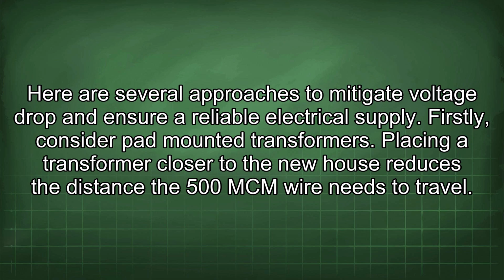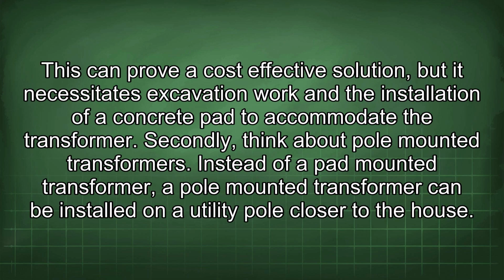Firstly, consider pad-mounted transformers. Placing a transformer closer to the new house reduces the distance the 500 MCM wire needs to travel. This can prove a cost-effective solution, but it necessitates excavation work and the installation of a concrete pad to accommodate the transformer.